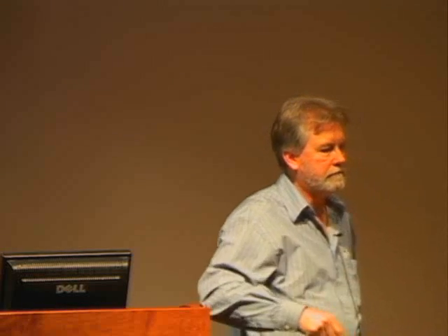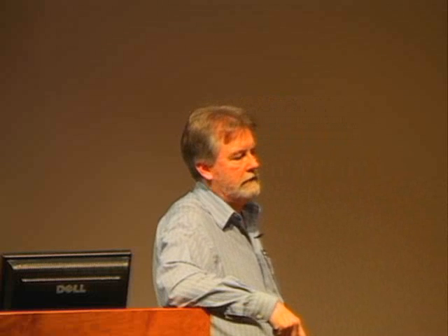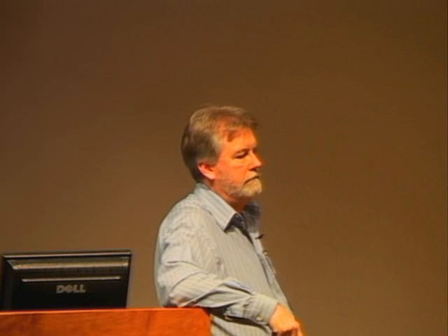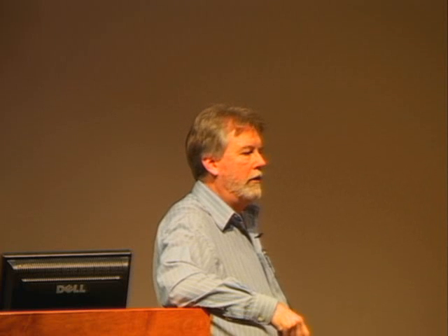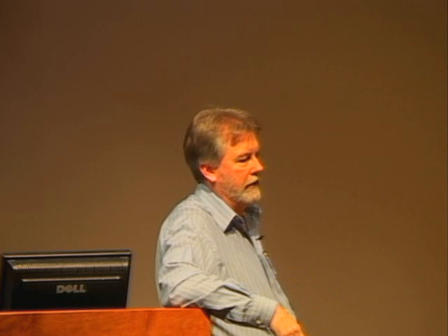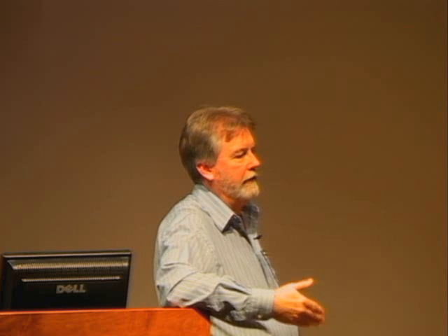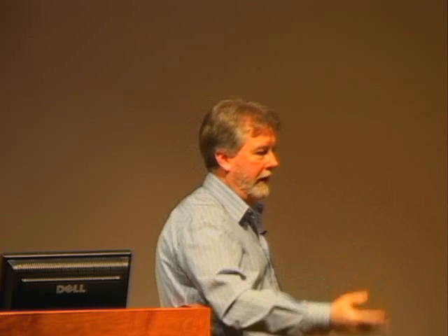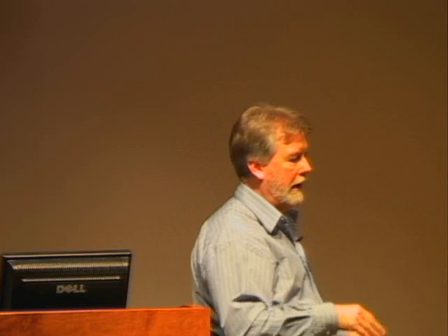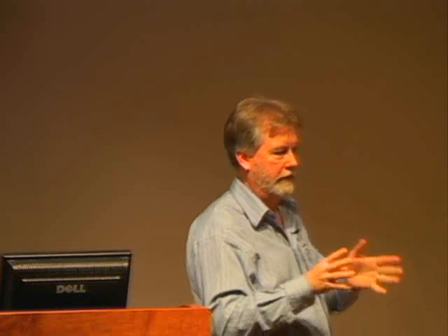I'm talking about real-time issues. If in real time I do this or that, it might push the system toward an edge. Is there a real-time mechanism to coordinate this? Well, I think that goes into the planning studies. Nothing will be done in real time unless somebody has simulated it with the standard studies and standard models, and said, I've tested this scheme, this operating behavior, this contingency, this relaying scheme. We've tested it all together, and we all agree it's okay to do it. So they'll have studies showing what happens under all these conditions. Nobody will take an action that hasn't been studied. That's how it's done.